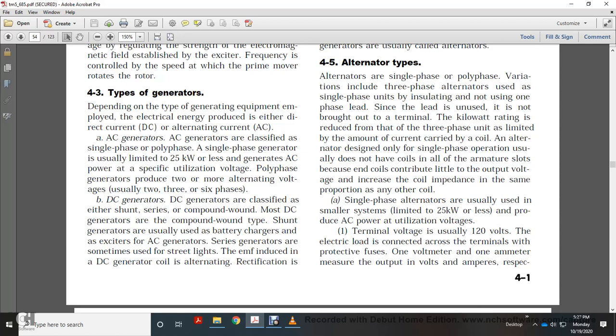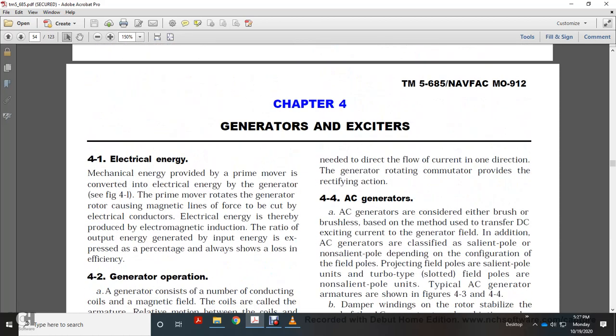A single phase generator, usually 25 kilowatts or less, generates AC power at a special utilization voltage. Polyphase generators produce two or more alternating voltages, usually 2, 3 or 6 phases. DC generators are classified as shunt, series, or compound wound. Shunt generators are usually used for battery charging and to excite AC generators. Series generators are sometimes used for street lights. The electromotive force induced in the DC generator coil is alternating, so rectifying is needed to direct the flow of current in one direction. A rotating commutator provides the rectifying action.